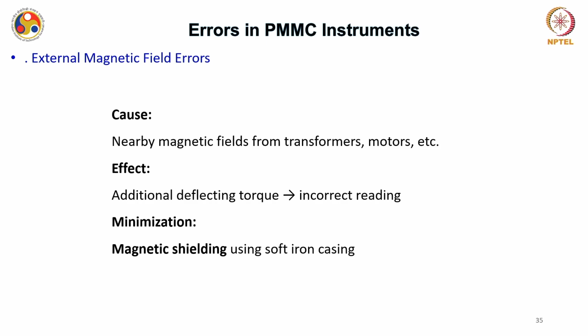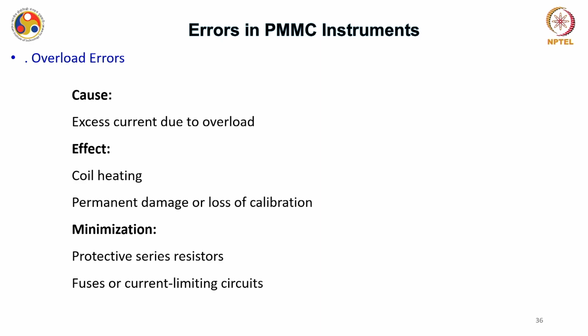Fine. So, then there are other errors like external magnetic field errors, which are unavoidable. Nearby magnetic fields from transformers, motors, etc. can hamper the magnetic field of the permanent magnet available in the instrument. Okay. So, this may result in additional deflecting torque, which is not desirable, and it can lead to incorrect readings. Okay. Minimization can be done by using magnetic shielding. This magnetic shielding is mostly done using materials which have fast magnetization and fast demagnetization also. So, in these cases soft iron can be used. That is a perfect example of a material which can be used for covering it, or say protecting it from external magnetic fields. Okay.